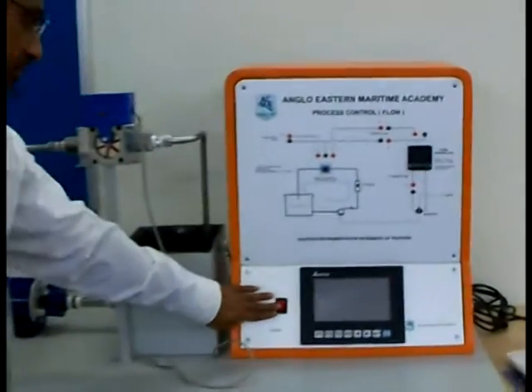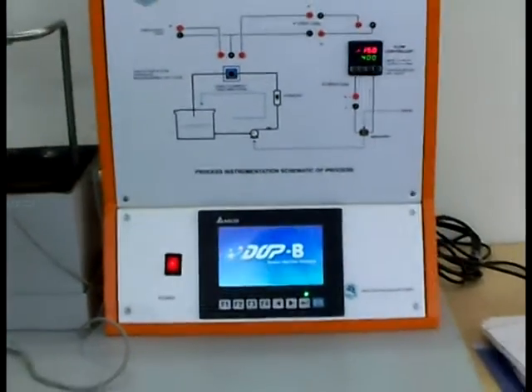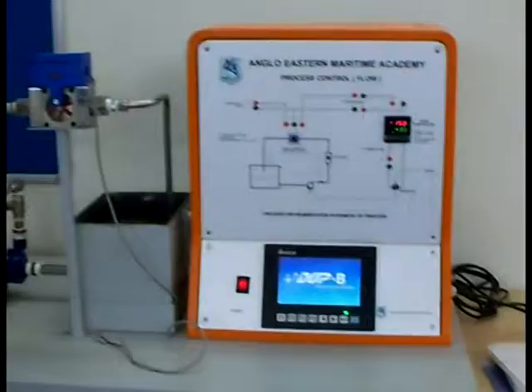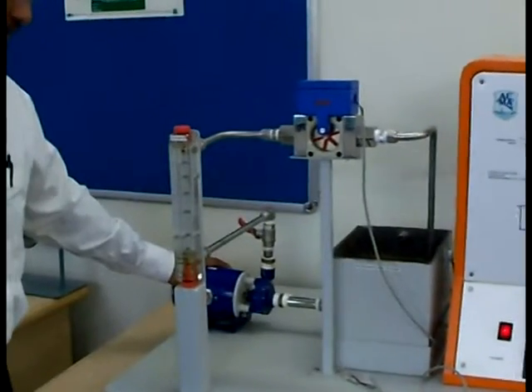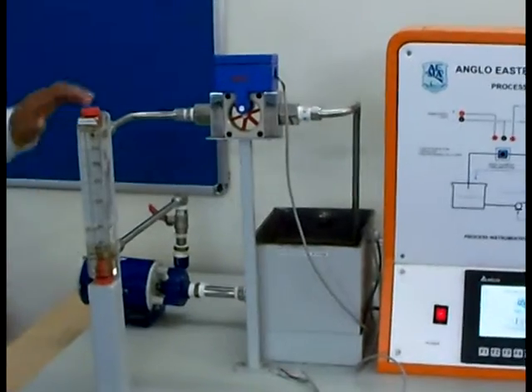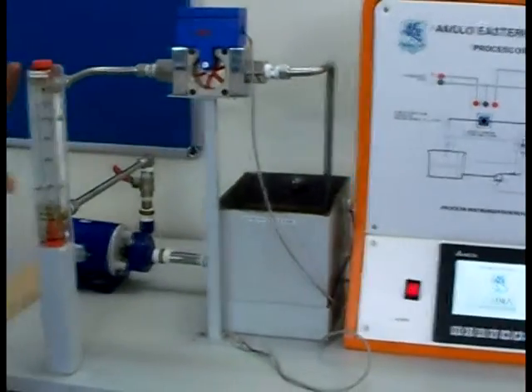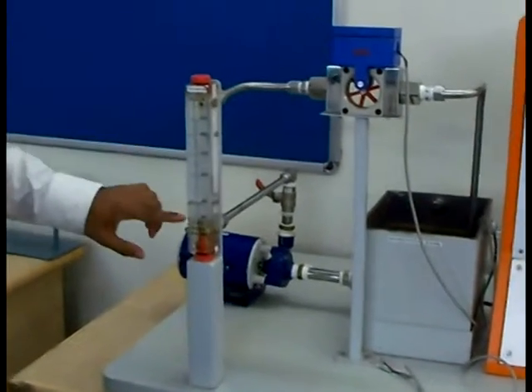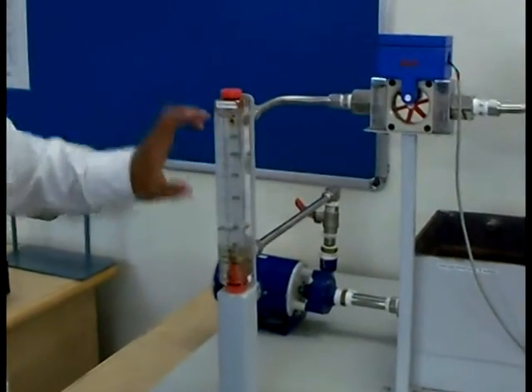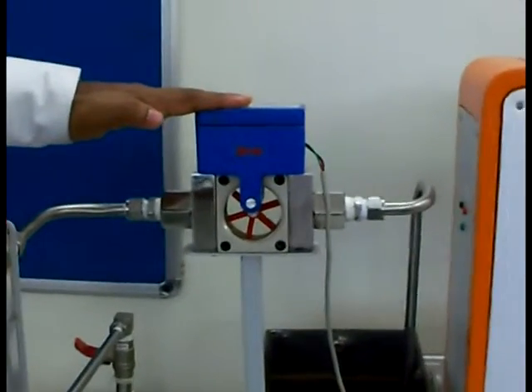This is the new flow control trainer built by Aema. We essentially have a centrifugal pump that takes suction from this tank, delivers through a flow meter, through a flow transmitter, and back into the same suction tank. We have a rotameter calibrated from 50 to 500 liters per hour, and the flow transmitter is rated at 0 to 600 liters per hour.